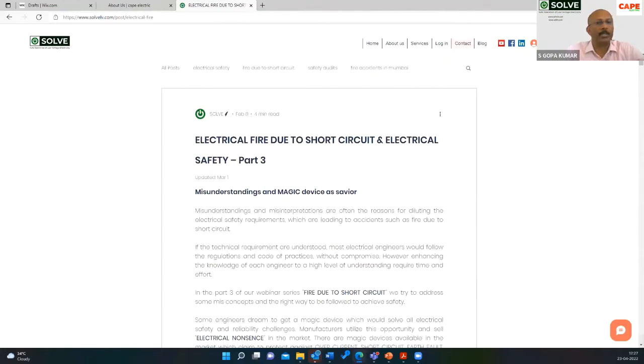Please use this method. So now the question, fault loop impedance. As a protective measure in a TN or a TT system, you are having an MCB. The purpose of the MCB is, during an overcurrent, such as an overload or a short circuit or an earth fault, your MCB is supposed to trip. Now, in an earth fault, in order to find out whether the MCB is tripping or not within the specific time, multiples of the rated current should flow through the MCB. For example, a type C MCB requires 10 times its rated current to disconnect within 0.2 seconds. Means a 63 amps MCB requires 630 amps current to flow through it. Then only it will trip within that particular specific time.